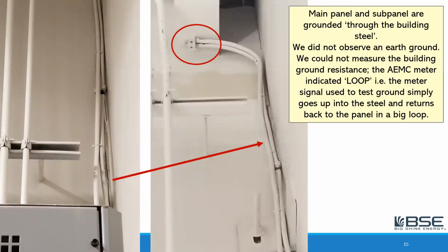Here you can see if we were to scan over to the corner of that array of electrical equipment, we would see heavy cables going up to one of the I-beams in the building. So here, this is the main building ground, and it's connected through the building steel, as we call it. In other words, the ground doesn't go directly to the earth, it goes into the steel structure of the building. And so it, first of all, makes it difficult to measure the building grounding with that kind of system, because if you put a meter on there, a clamp meter, and I'll show you the type of meter that we use, it's made by AEMC, it'll indicate loop when you try to read resistance, because the signal will just go up into the building steel and come right back again. It never went into the ground, and it can't tell you what the ground resistance actually is.